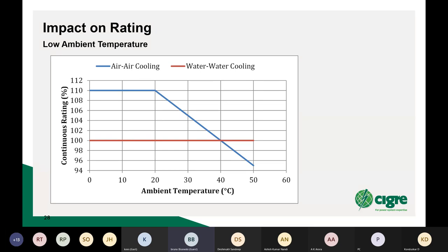And the rating is, of course, governed by the hotspot temperatures in your devices and the junction temperature in your switching devices. So as the temperature goes up, that junction temperature rises and the rating has to go down as the temperature goes up. You can, of course, design to any temperature you want, but then the cost goes up. So to get the sort of 110% or something, you have to buy extra cooling if you would like the overload.